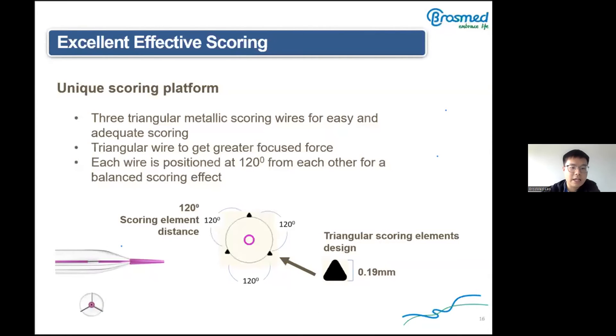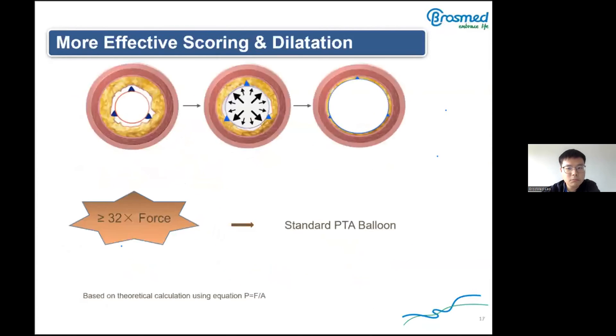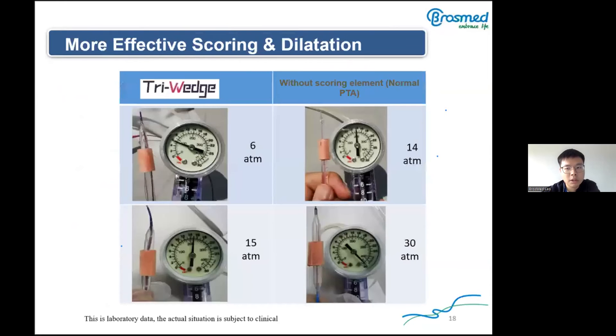Each wire is positioned at 120 degrees from each other for a balanced scoring effect. Based on theoretical calculation using the equation pressure equals force divided by area, the pressure caused by the Tri-Wedge is 32 times that of a standard balloon under the same force. We compared the Tri-Wedge and a normal balloon without scoring elements to expand a simulated calcified lesion, and the Tri-Wedge required lower pressure to dilate it.